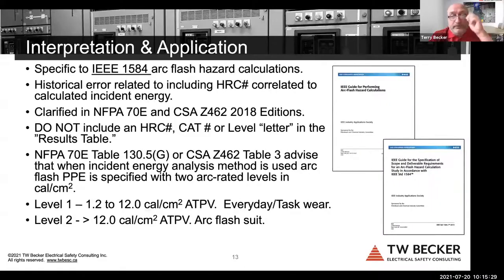Now I'm going to talk about 1584 briefly again. Like I said, I'm probably already running over, but there have been problems historically with IEEE 1584 and its application and the reports issued by PEs in the US. There is no correlation between hazard risk category, arc flash PPE category, level letter, or level number that should be included in an engineer's report. There never was a correlation, and it's actually taken industry down a rabbit hole. Even the electricians and other qualified workers, we do not call arc flash PPE by a category and HRC number. We call up arc flash PPE with an arc thermal performance value in calories per centimeter squared. That's what the worker needs to know. We shouldn't be talking about categories when we have IEEE 1584 arc flash hazard calculations completed. We need to continue to work on this. This needs to be fixed.